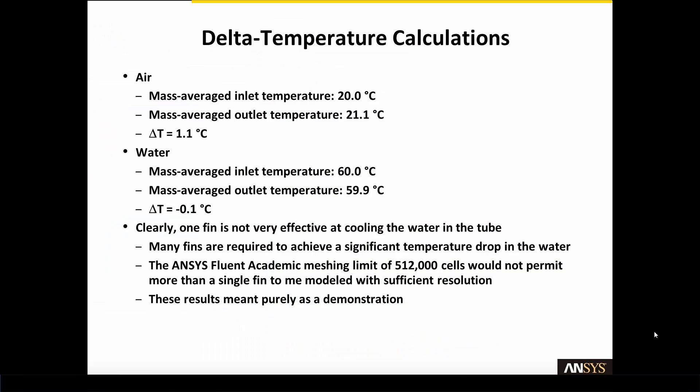Now let's look at some delta temperature calculations. For the air the mass average change in temperature is about 1.1 degrees C. And for the water the mass average change in temperature is 0.1 degrees C. Clearly one fin is not very effective at cooling the water in the tube. Many fins would be required to achieve a significant temperature drop in the water which is the point of the heat exchanger.